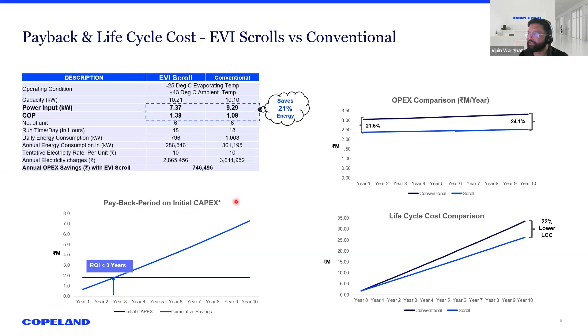Right. So these two technologies, variable speed and the EVI, put together, are what has been put into Ecozen's cold room solution. So how is it helping? As you know, the sun intensity will not be constant throughout the day. In the morning, because of low solar radiation, the intensity will be lower, and it will be at its peak during noon, and then during the second half, towards the evening, it will again go down. So there will be a lot of variation in the power that will be generated to refrigerate the goods that are stored inside the cold room.